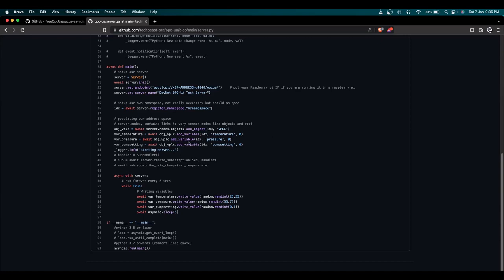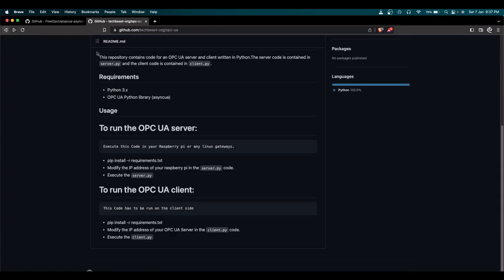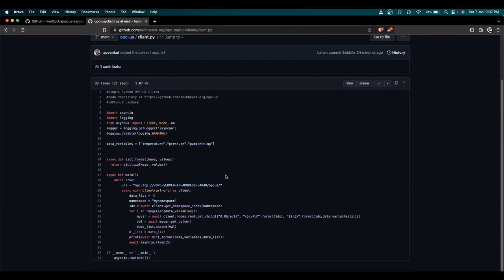Now we create an object. As I covered in the theory video, the OPC UA address space contains variables and methods — everything is an object. My object here is 'vPLC' — a virtual PLC. I'm adding variables to it: temperature, pressure, and pump setting. The server runs in an infinite loop, writing values using the random function. Temperature is randomly set between 25 and 35, pressure between 55 and 75, and pump setting is randomly 0 or 1. Every five seconds these values are written.